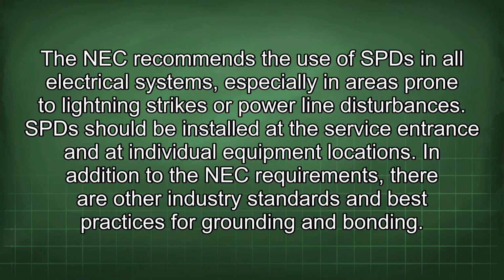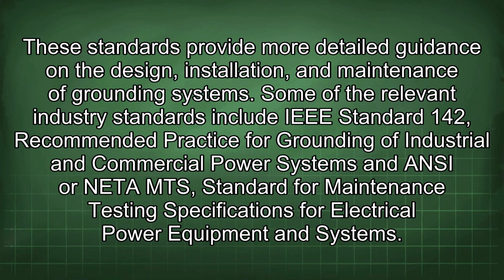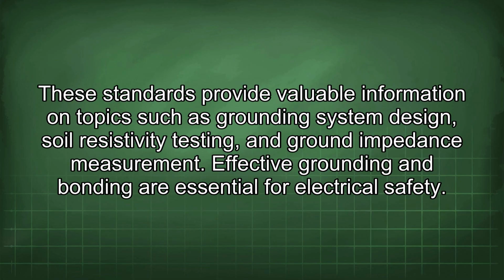In addition to the NEC requirements, there are other industry standards and best practices for grounding and bonding. These standards provide more detailed guidance on the design, installation, and maintenance of grounding systems. Some of the relevant industry standards include IEEE Standard 142, Recommended Practice for Grounding of Industrial and Commercial Power Systems, and ANSI/NETA MTS Standard for Maintenance Testing Specifications for Electrical Power Equipment and Systems. These standards provide valuable information on topics such as grounding system design, soil resistivity testing, and ground impedance measurement.